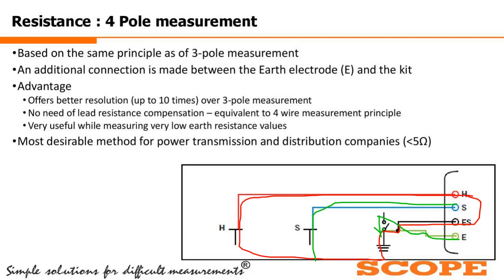So it is very similar to Kelvin's four-wire measurement method, or the four-wire principle. As the four-wire principle does not require test lead resistance or lead resistance compensation, here also we do not require any compensation of leads. It is very useful while measuring very low earth resistance values.